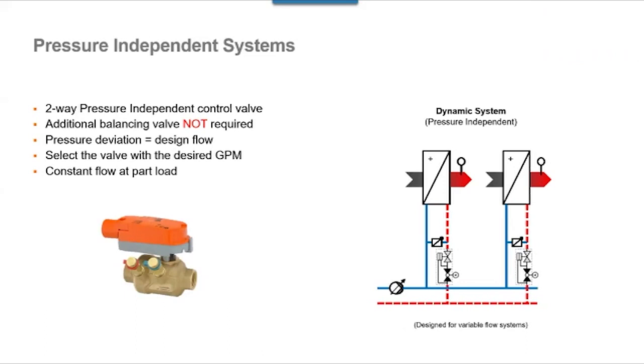It certainly helps on the labor side, but what I'm more interested in is that I don't have the design flow changes due to pressure. Now, with the pressure independent valve, you don't need Cv. So my tools of sizing control valves kind of go away, because you buy a pressure independent valve based on the design flow. A fully open PI valve provides X GPM. You want one that matches what the coil is doing. And again, more importantly, it's constant flow at part load.